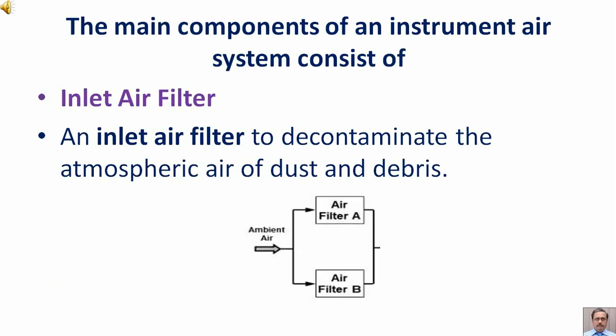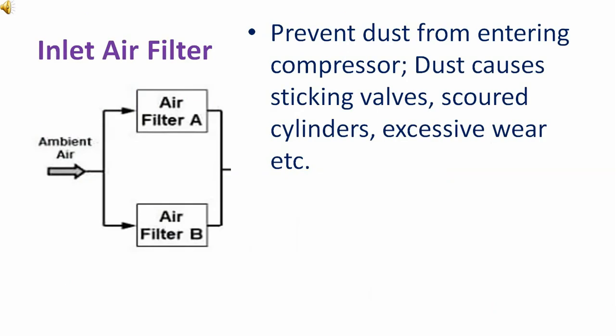The main components of an instrument air system: First is an inlet air filter to decontaminate the atmospheric air of dust and debris, and to prevent dust from entering the compressor. Dust causes sticking valves, scored cylinders, excessive wear, etc.